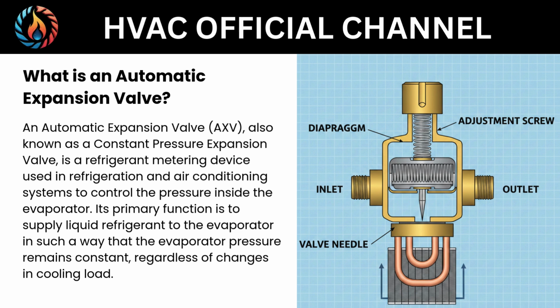What is an automatic expansion valve? An automatic expansion valve, AXV, also known as a constant pressure expansion valve, is a refrigerant metering device used in refrigeration and air conditioning systems to control the pressure inside the evaporator. Its primary function is to supply liquid refrigerant to the evaporator in such a way that the evaporator pressure remains constant, regardless of changes in cooling load.